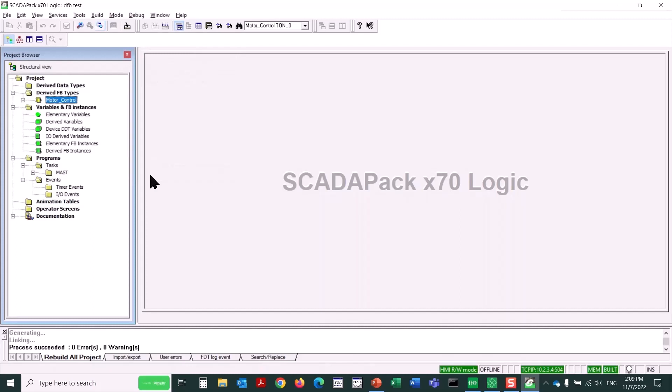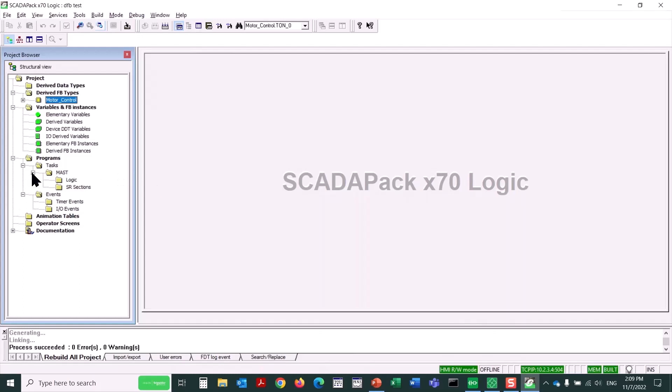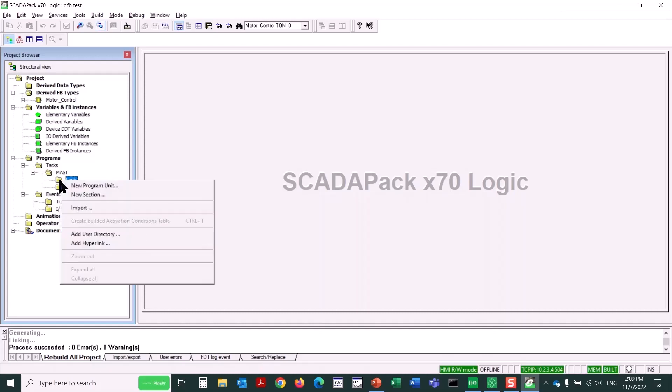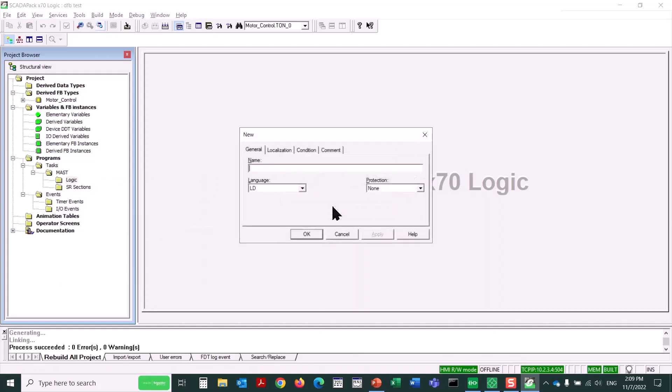Now we want to actually use this new derived function block. To create a new main program logic section, I'll expand the MAST, or Master Logic folder. I'll select the logic folder, where logic sections are actually created. Right-click on it and say New Section. Yes. Now I'll name this Station. And I'll use a language of function block diagram in this case. Click OK.